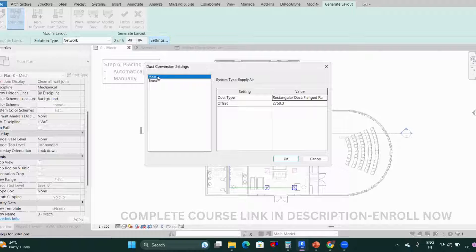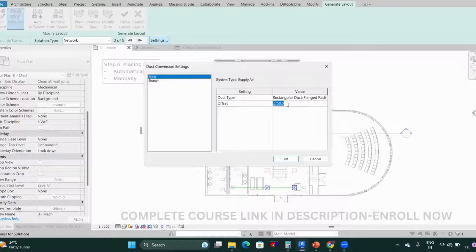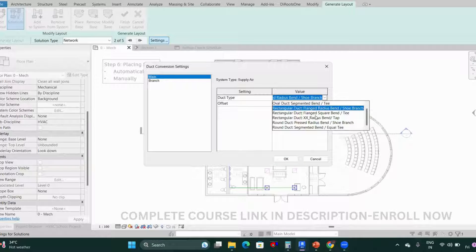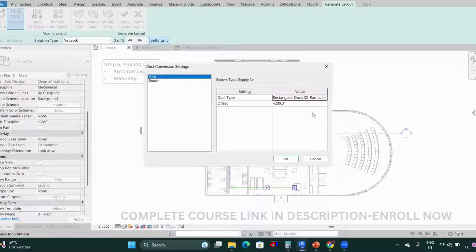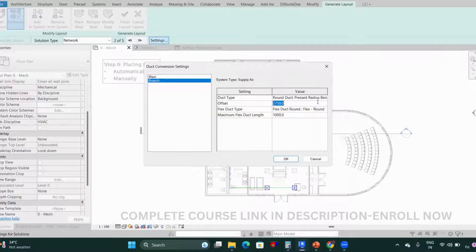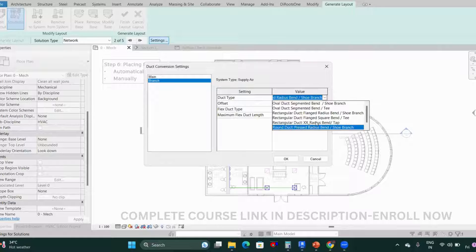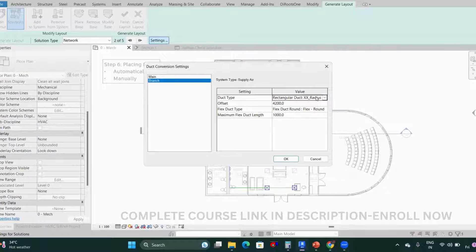In settings, we have two sections: Main and Branch. For Main, set the offset — which is the height of the duct — to, say, 4200. Select the duct type you created, for example Double X Radius. Then go to Branch, set the same offset, and select the same duct type. Click OK.